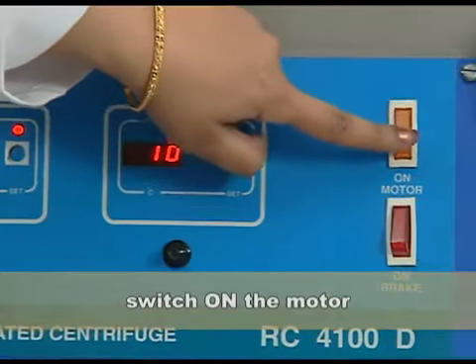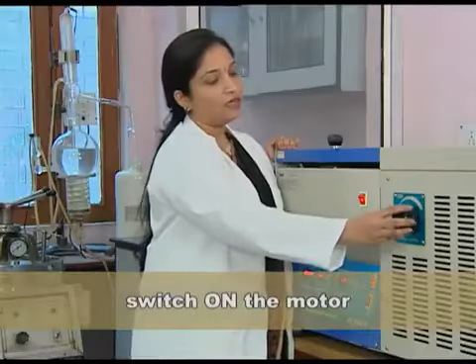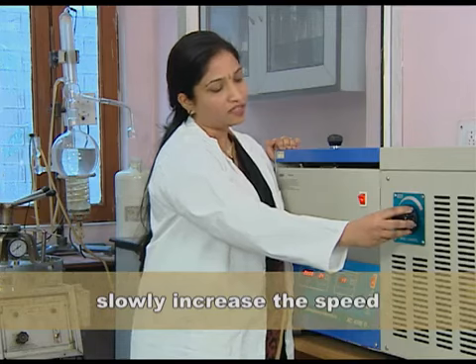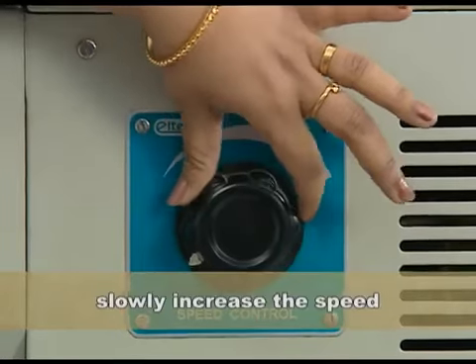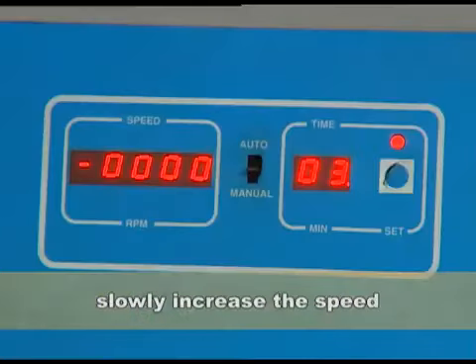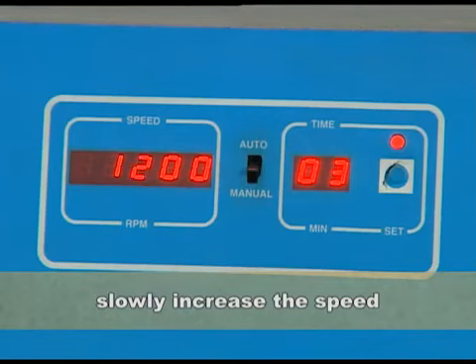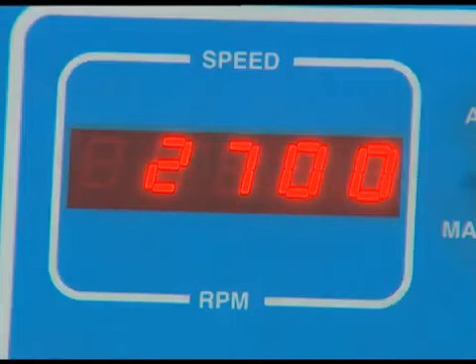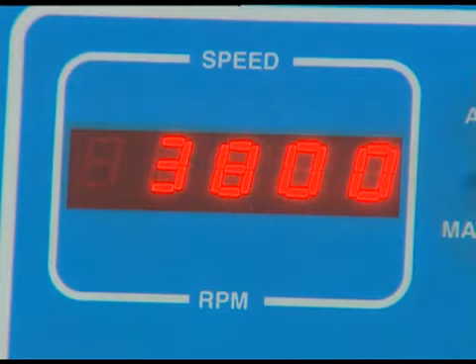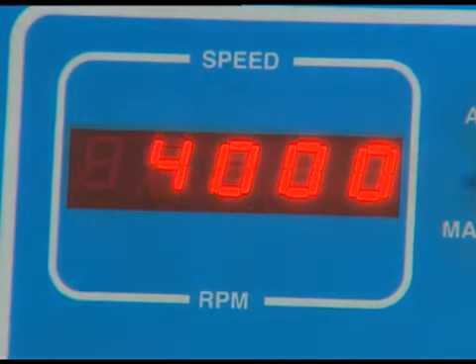Now let me put on the motor and let's slowly increase the speed to 4000 RPM. Now it has become 4000. Now the machine will run for another 2 to 3 minutes.